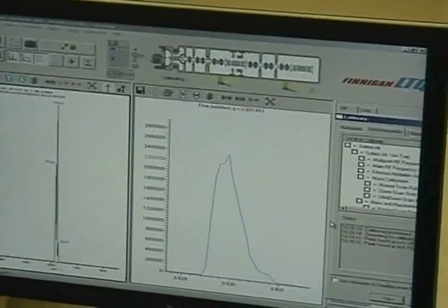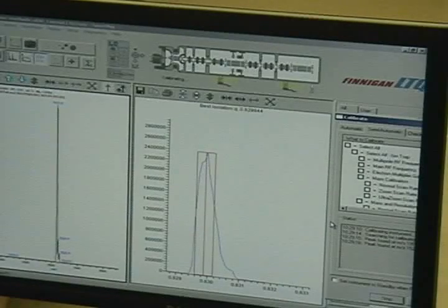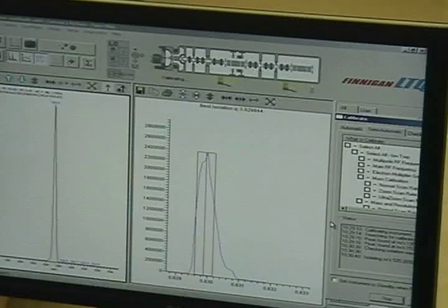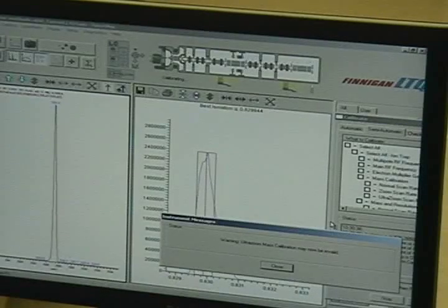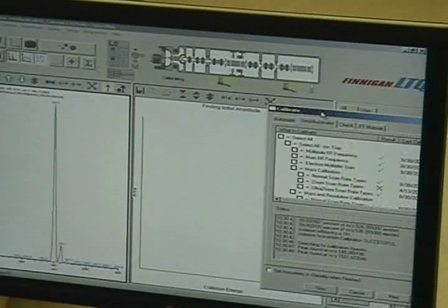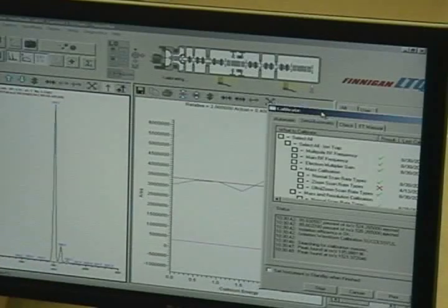So this step is to check the mass accuracy. Not mass accuracy, it's Q frequency accuracy. What we want to know is, when we want to isolate that ion, is the Q the same for every mass? Does the Q keep the same for every different mass? The Q of ejection? Yes.